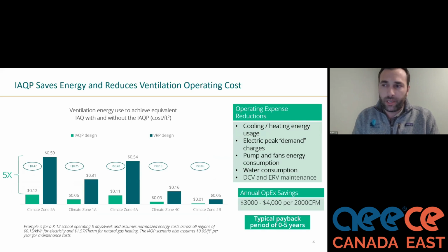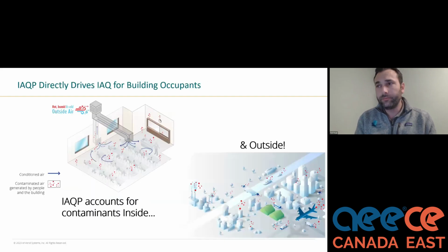When you're looking at various climate zones, I mentioned the cost of filtration versus the cost of energy. You can see here that the IAQp designs, in terms of a cost per square foot to ventilate those buildings, are significantly reduced with the IAQp because we're strictly bringing in less outside air.